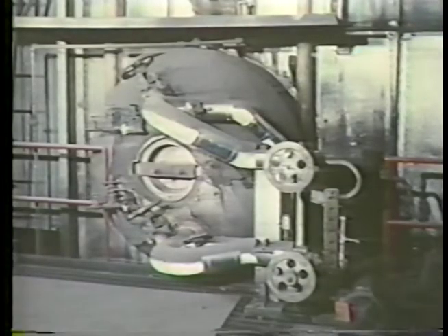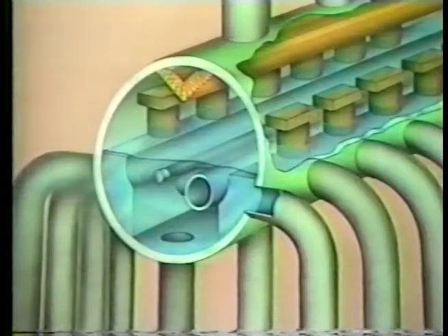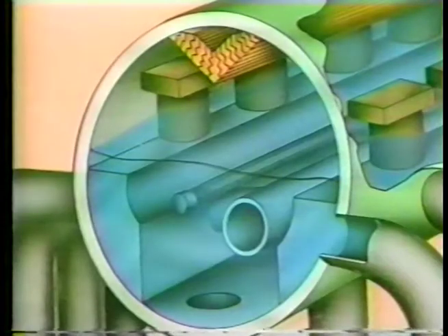Once the walkthrough is complete, the next step in the startup procedure of a drum-type boiler is the filling of the steam drum and waterside components. The steam drum holds a large quantity of water for the production of steam. The drum also directs boiler water to the headers and water wall tubes. In preparation for startup, the operator opens the valves that control the flow of feed water to the economizer inlet and boiler water to the drum.